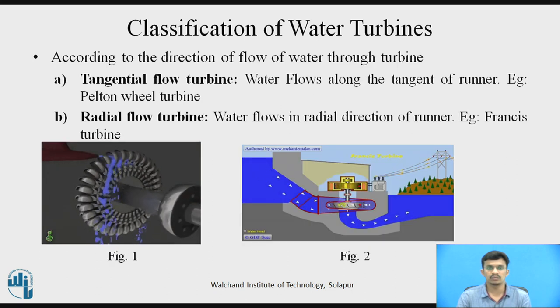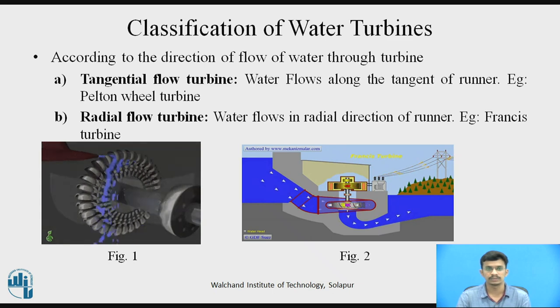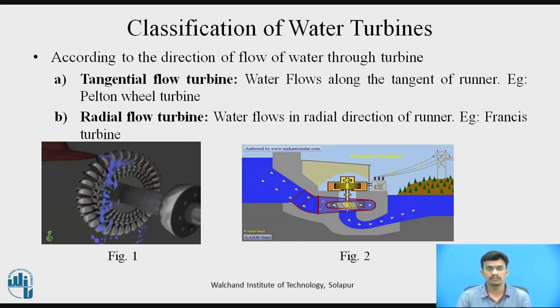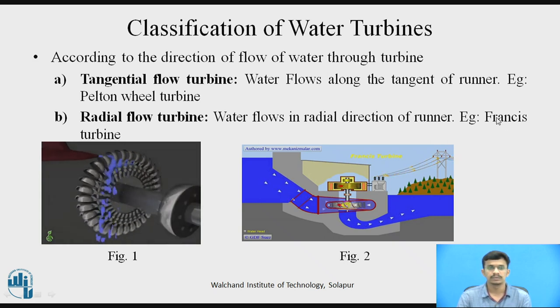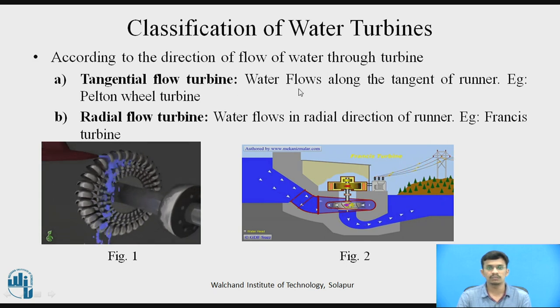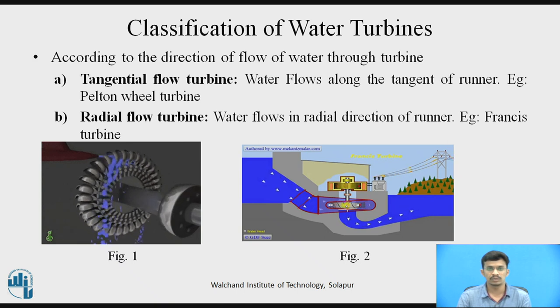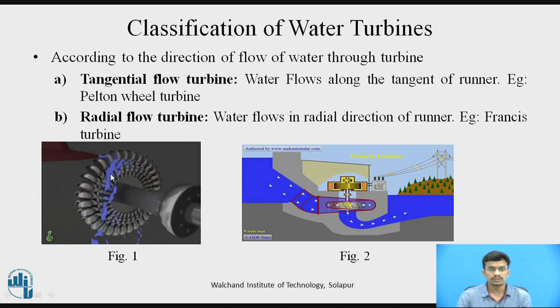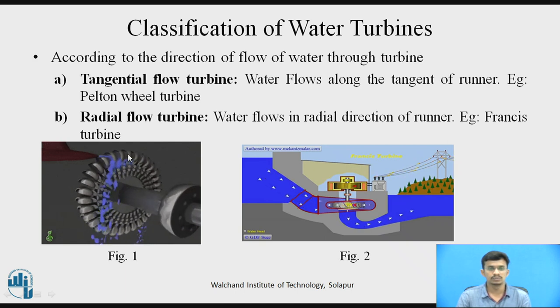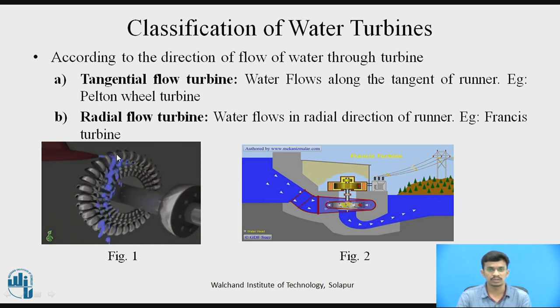According to the direction of flow of water through the turbine, we classify turbines into four subtypes: tangential flow turbine, radial flow turbine, axial flow turbine, and mixed flow turbine. In the tangential flow turbine, water flows along the tangent of the runner. The example is the Pelton turbine. As shown in figure one, with the help of a nozzle, a water jet is applied to the runner, with the direction of water along the tangent to the runner.